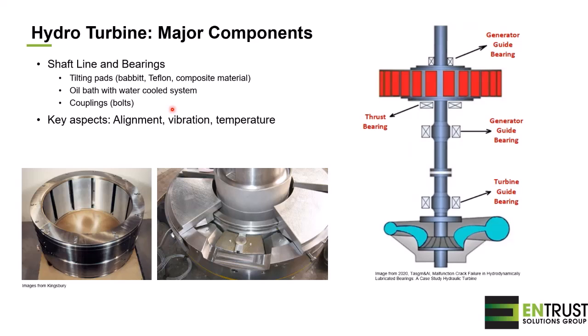Another major component of a hydro turbine is the shaft line and the bearings. We usually find a turbine guide bearing at the bottom, another one underneath the generator, and one above. And all the weight of the shaft line is taken by the thrust bearing, which is usually underneath the generator or above the generator. Here, sometimes we talk about a combined bearing because we can find the thrust and the guide bearing together.